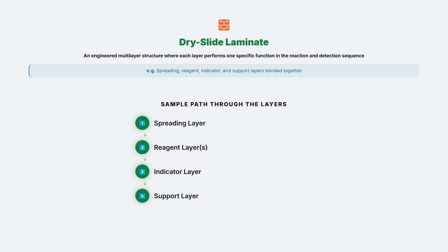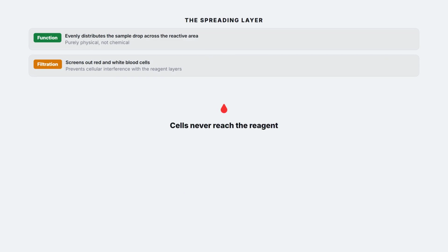A colorimetric dry slide is a genuine engineered laminate, typically 4 to 5 distinct functional layers bonded together, each performing one specific job in sequence as the sample migrates downward through the structure. The spreading layer sits on top, and its job is purely physical, not chemical, distributing the sample drop evenly and rapidly across the slide's full reactive area. Typically a microporous, non-woven or woven fabric structure, it also performs a critical filtering function, screening out red and white blood cells, preventing them from ever reaching the reagent layers beneath.